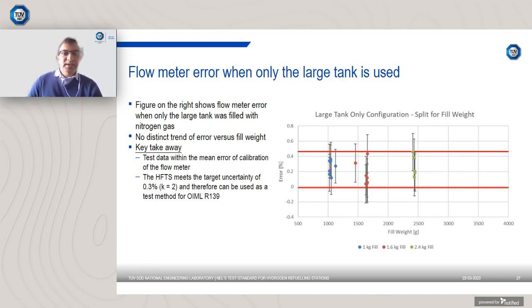Now, the data shown here is when we used only the large tank. And in this case, again, what you can see is that there is no distinct trend of error versus fill weight. So again, because the data points are within the mean error of calibration for the flow meter, we can essentially say that, once again, we could even use the large tank only for verification of a dispenser with respect to OIML R139.